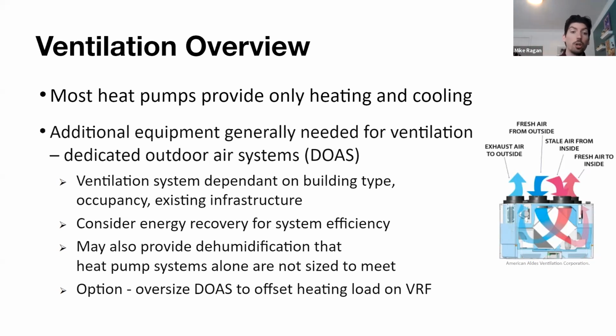But in addition, DOAS systems can also provide dehumidification that heat pump systems alone are not sized to meet. So if you have a dehumidification-heavy type of application, I would caution you to not just assume that the heat pump will be able to do it. Certainly we could tie in, and certainly we want to take a look at that application. But the equipment as designed wasn't meant strictly for large dehumidification loads. So we will want to take a look at that in a nuanced way to ensure that we deliver the air requirements to the space.